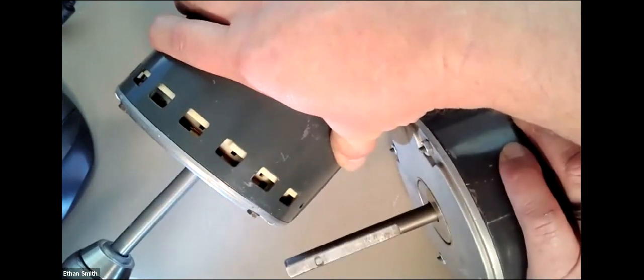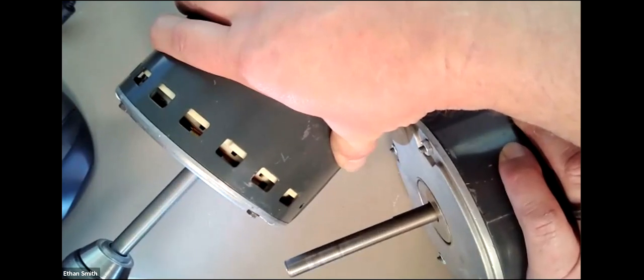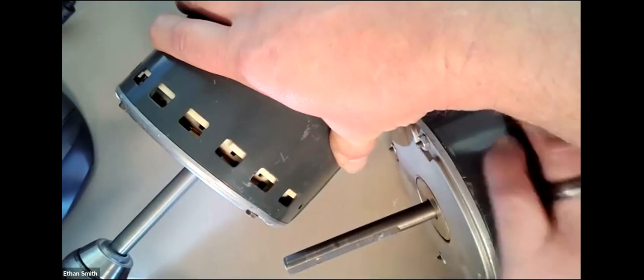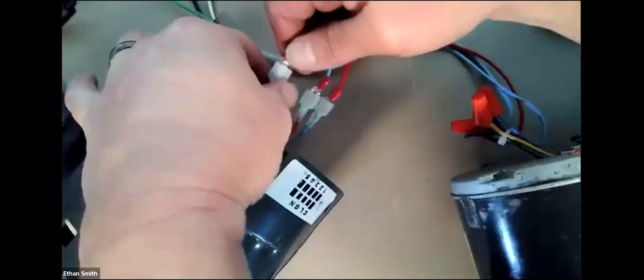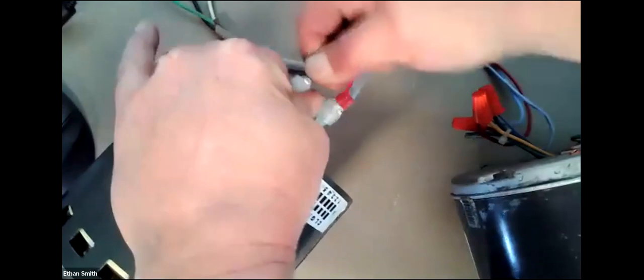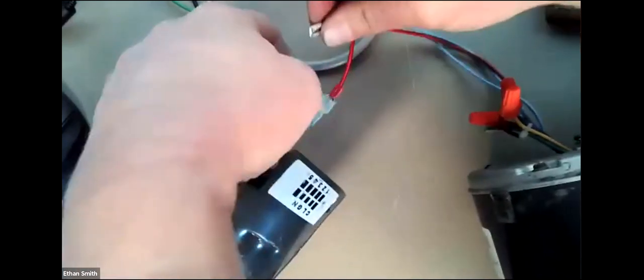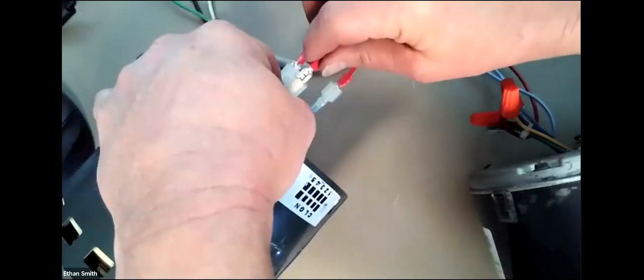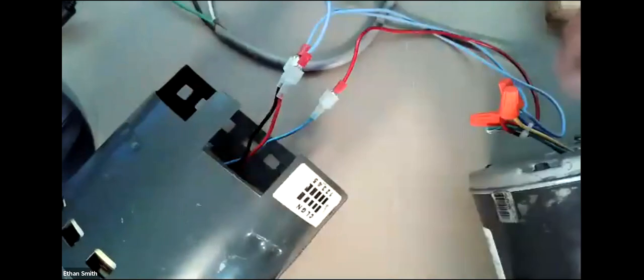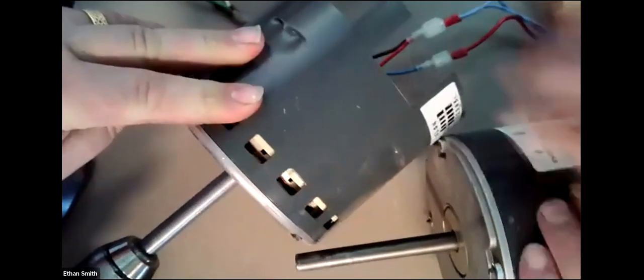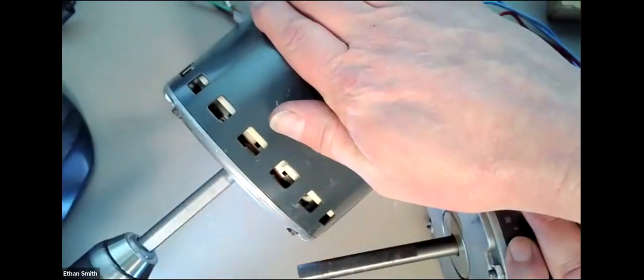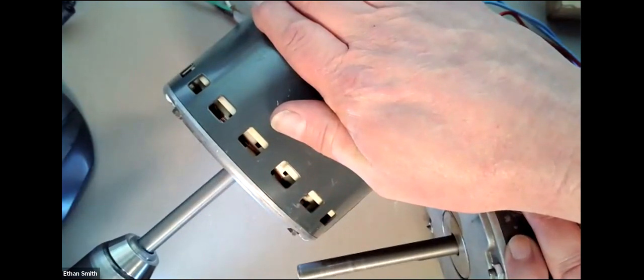Here's the cool thing about three-phase. If we want them to operate the opposite direction of what it currently is operating, all we have to do is switch two wires. So if you ever go out to a rooftop unit and you've got a fan moving backwards, hopefully your spade terminals aren't as tight as ours. No, maybe we hope they are actually. You can simply take two wires and reverse them. We just took two wires there, reversed them, and go ahead and start this. And you can see they're spinning in the same direction now.